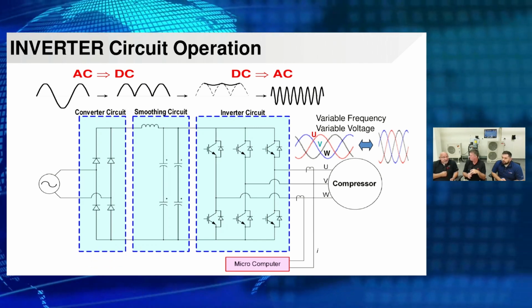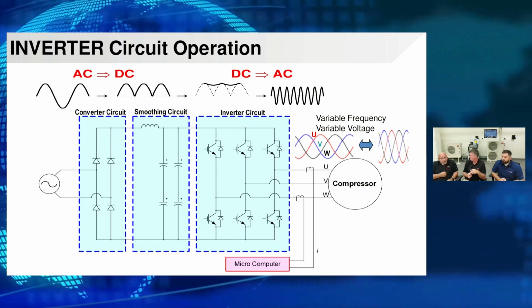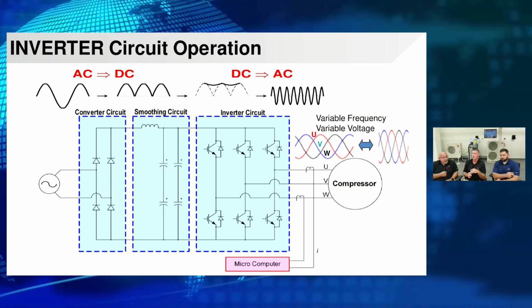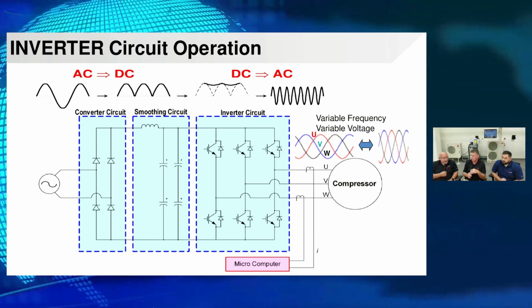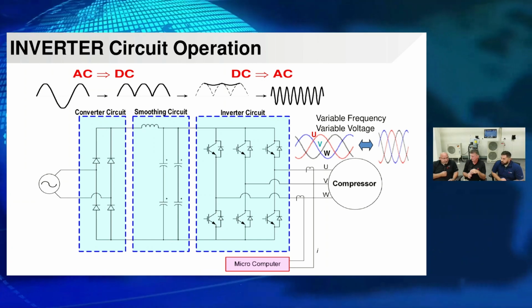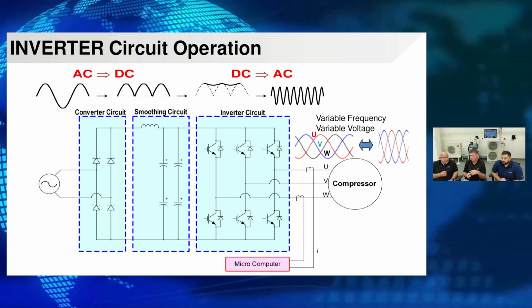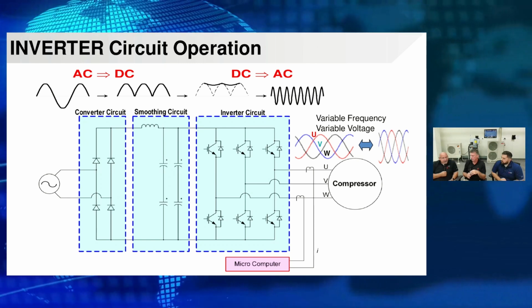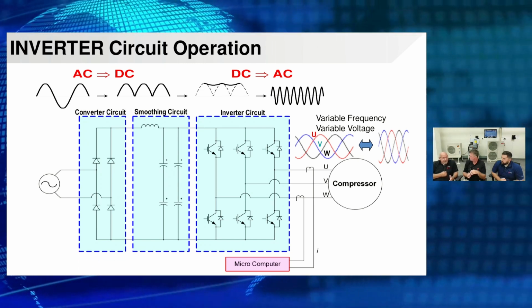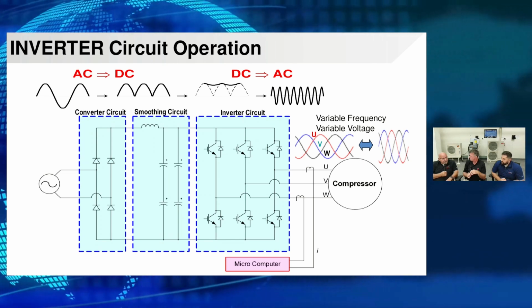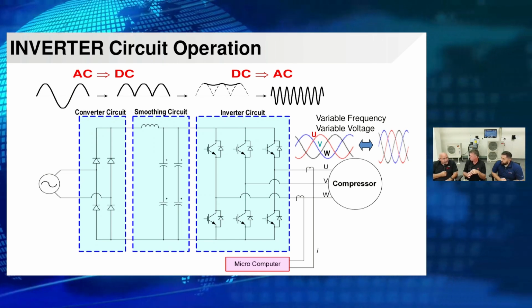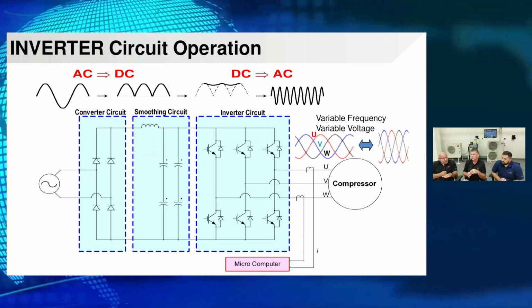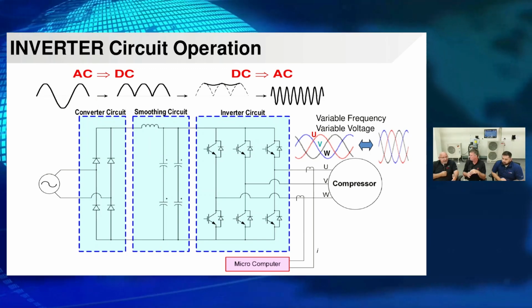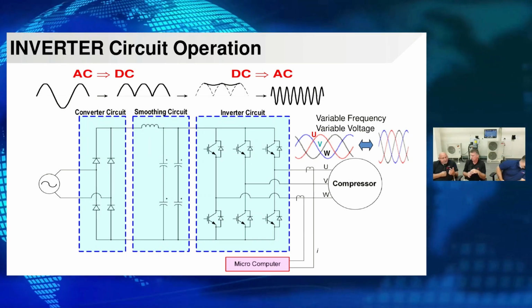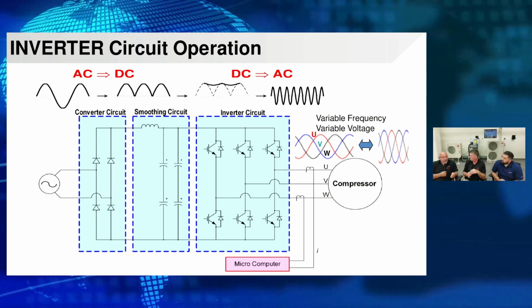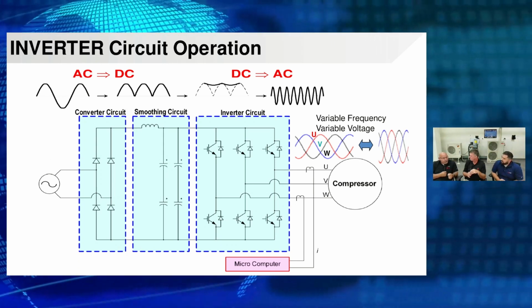So we need to send that DC signal to our smoothing circuit. In the smoothing circuit two components are found: the reactor, which is like a choke, and then the capacitors. When you pair a capacitor with a reactor, we straighten that DC circuit line as straight as we can. It's still a little choppy, but not as bad as when it first was introduced. There's only one component made on Earth that can generate a true DC signal.